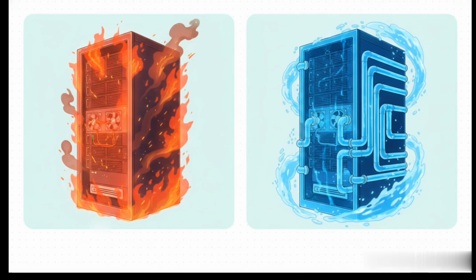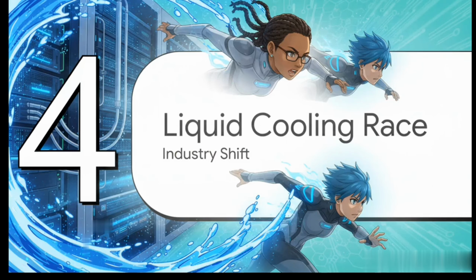Traditional air-cooled racks max out at around 15 to 25 kilowatts of power. But modern AI racks are already hitting 85 kilowatts today, with projections showing them demanding up to 250 kilowatts very soon. So it is physically impossible for air to cool the next generation of AI. Liquid cooling is no longer just a nice option, it is totally mandatory. And that leads us to our final stretch, Section 4: the liquid cooling race.